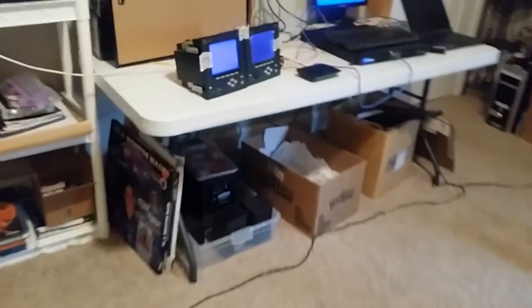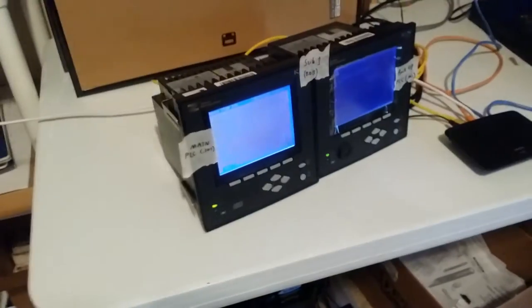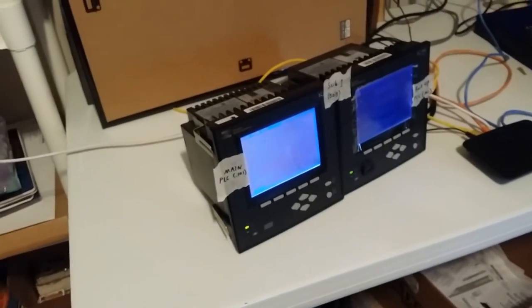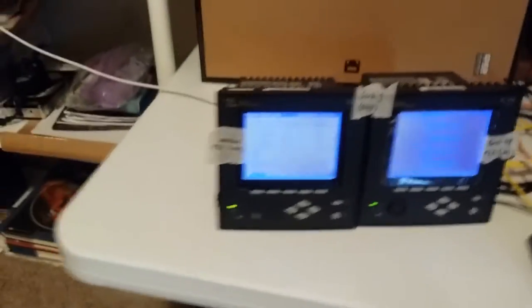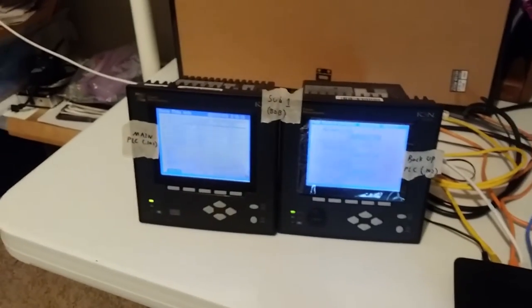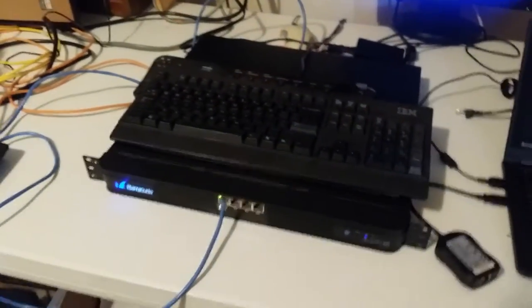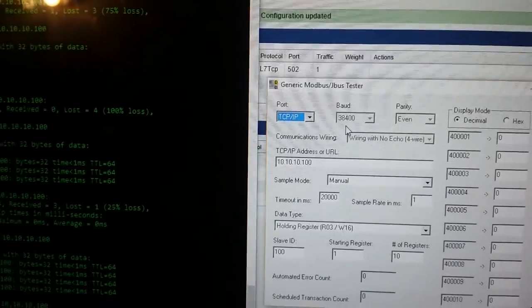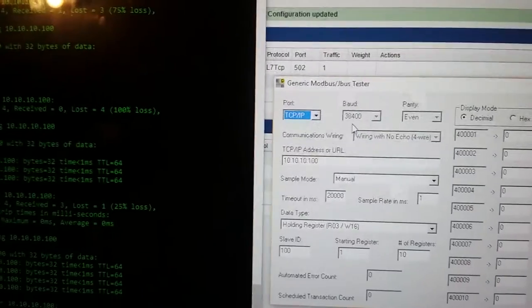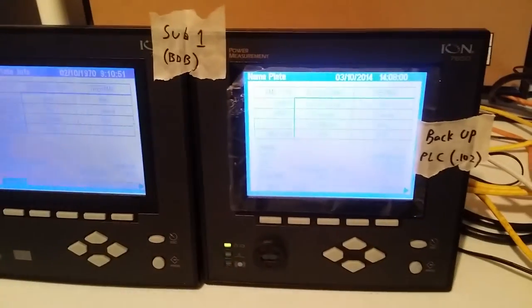So here we have some Schneider Electric smart meters programmed to simulate PLC registers. They are attached to a switch which then feeds into a larger switch, in this case it's supposed to be our fiber ring, and then the Barracuda hosts the virtual IP which we then point our clients to. You can see it's pointed to 100 but the meters themselves are 101 and 102.